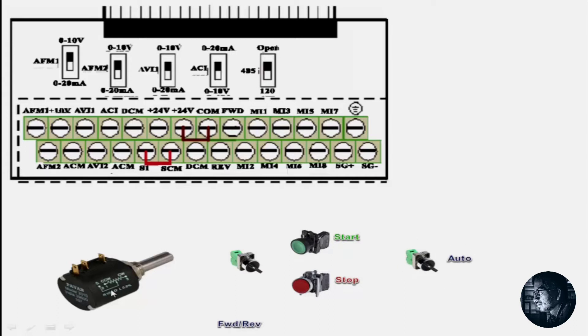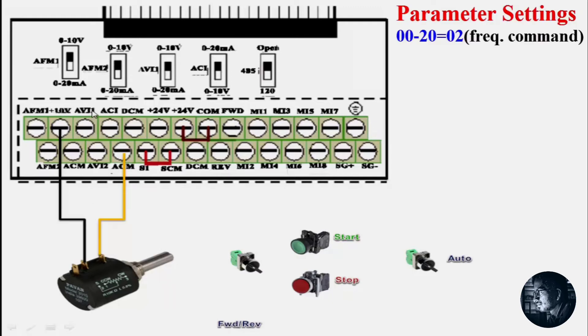First let's see the potentiometer wiring. On the potentiometer, the arrow marks the analog output, and pins 1 and 3 are the 0V and 10V power supply. We connect 10V to 10V and 0V to ACM (analog command). The analog output is connected to AVI, the analog voltage input.